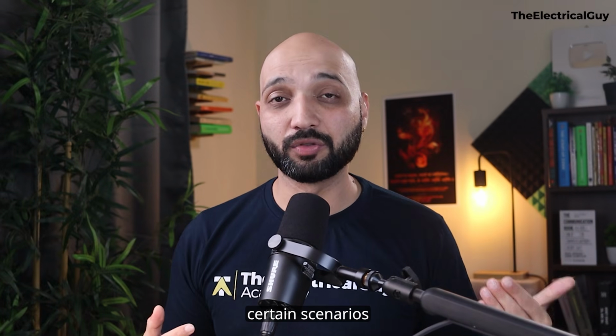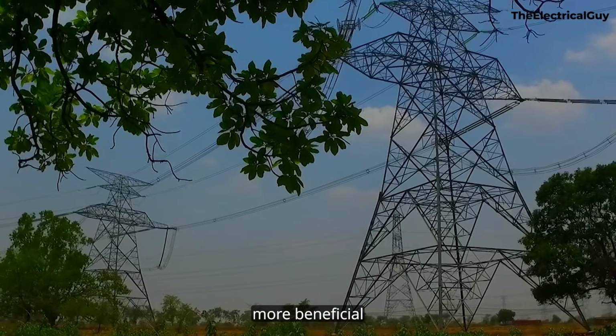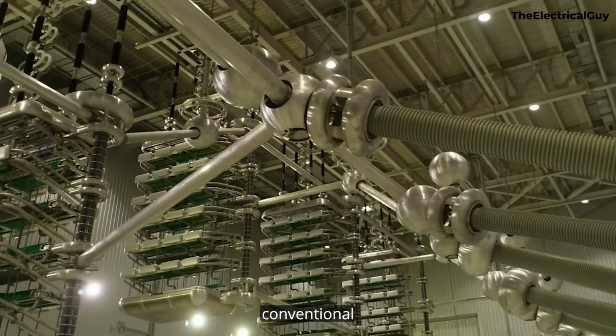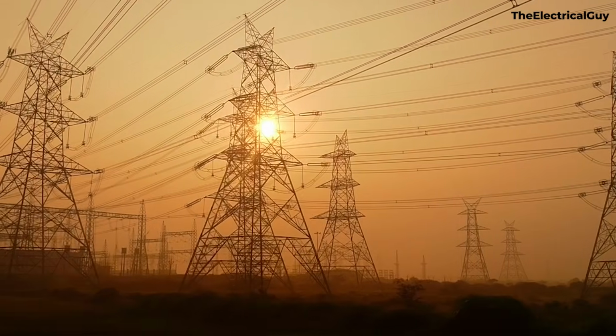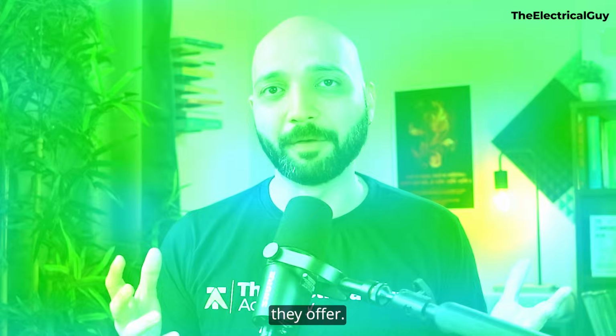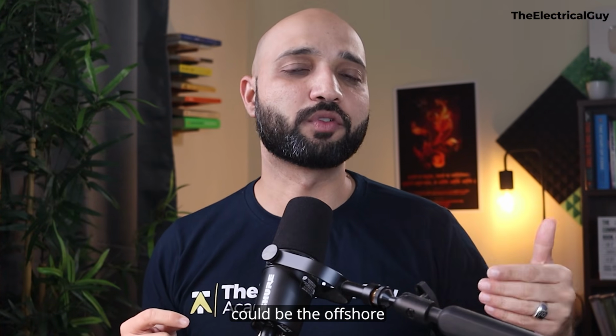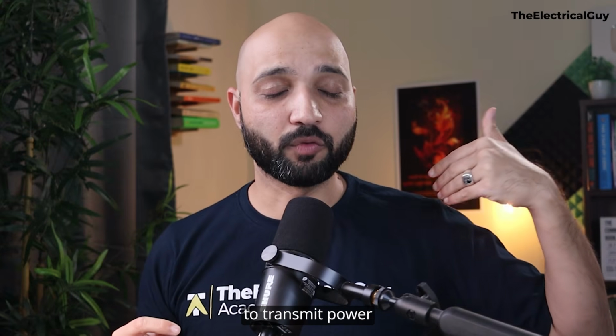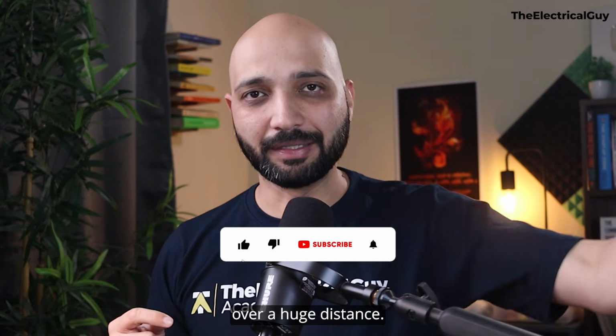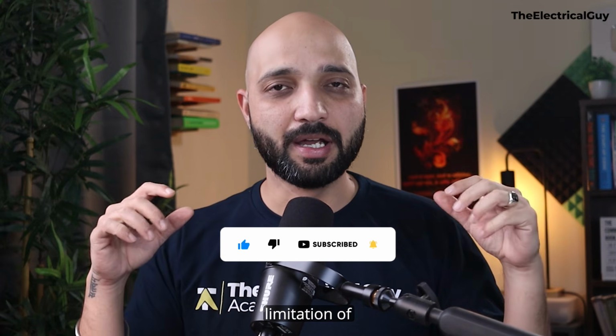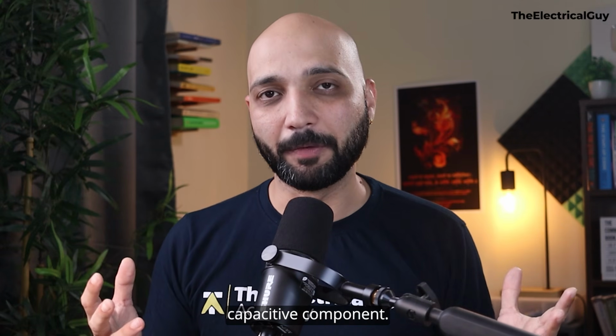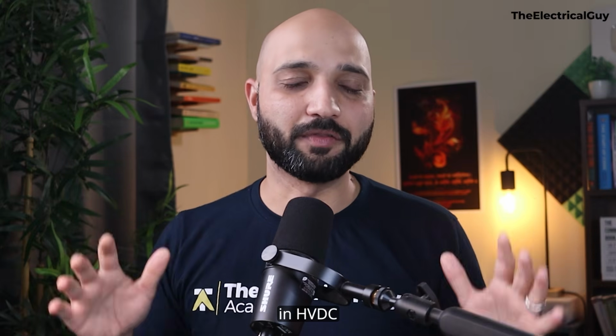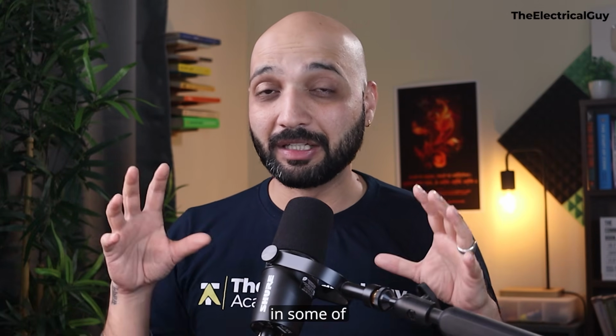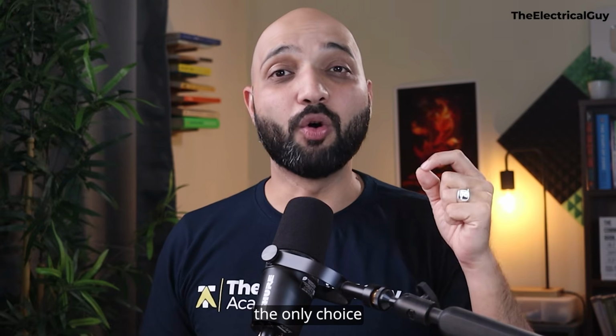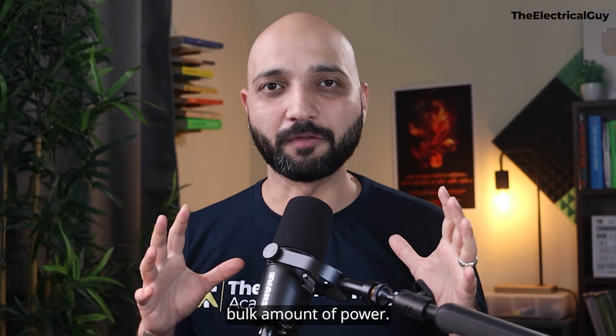There are certain scenarios where HVDC is much more beneficial compared to the conventional high voltage AC transmission. The reason is pretty simple, the advantage they offer. One such scenario could be the offshore transmission of power, where you have to transmit power over a huge distance, where AC is not very helpful because of the limitation of the inductive component and capacitive component. All those things are eliminated in HVDC transmission. And that's why in some applications, those are the only choice to transmit a bulk amount of power.